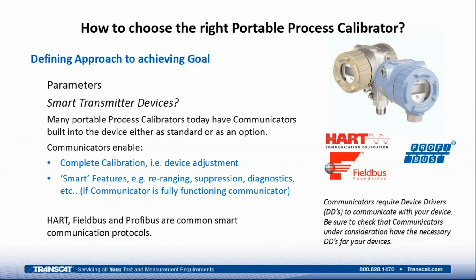An additional comment on communicators: they require device drivers to communicate with your device. So be sure to check that the communicators under consideration have the necessary device drivers for your devices. There are libraries and capabilities within the communicator to store additional device drivers, but if a device driver isn't present, you may be able to communicate with the device in a generic mode, but all of the features and functionalities may not be available to you through the communicator.